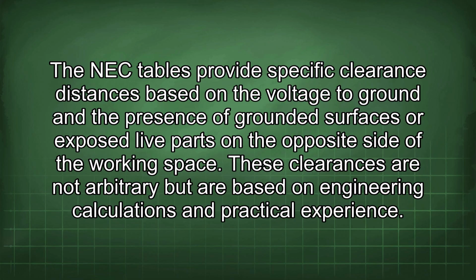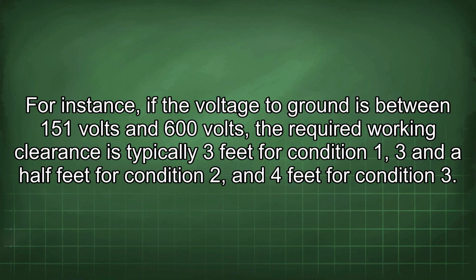The NEC tables provide specific clearance distances based on the voltage to ground and the presence of grounded surfaces or exposed live parts on the opposite side of the working space. These clearances are not arbitrary but are based on engineering calculations and practical experience. For instance, if the voltage to ground is between 151 volts and 600 volts, the required working clearance is typically 3 feet for condition 1, 3.5 feet for condition 2, and 4 feet for condition 3.